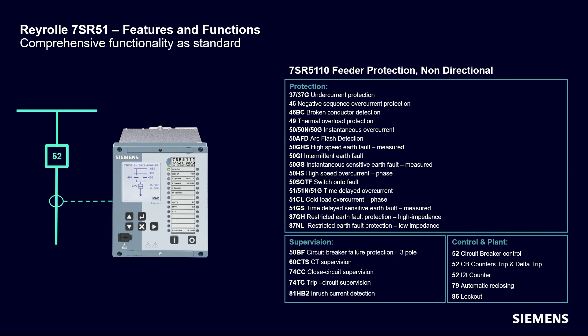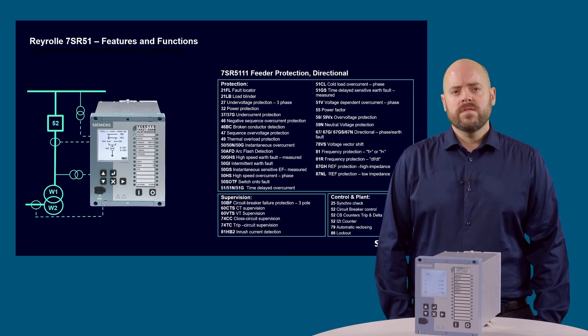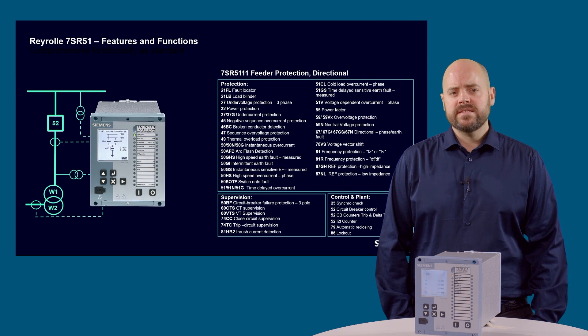High-speed, intermittent and sensitive earth fault protections 50GHS, 50GI and 50GS use a configurable automatic re-closing function 79, providing flexible independent automatic re-closing sequences for phase and earth faults to restore power flow after transient network faults. The device also has the option for direct arc flash detection inputs with high-speed tripping contacts for fast clearance when arc faults are detected, and temperature sensor inputs for connecting to sensors located in the plant.